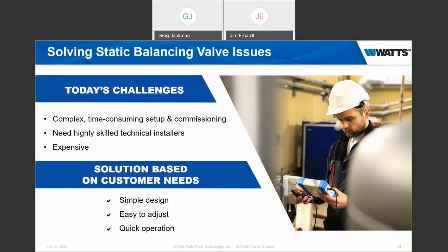As you start thinking about that, it's a complex, time-consuming setup and commissioning to go through, because again, once you balance one valve or one stack, you have to go back and balance the other. So basically, in a typical commissioning job using static balancing valves, you're typically running through anywhere from 3 to 5 times to get everything within specification or as close as you can possibly get it. So it is a very time-consuming job.